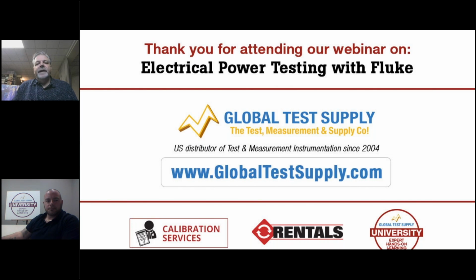If I need those accurate standards to justify a decision being made for product quality as a part of a quality program, or if I'm trying to satisfy a customer that what I'm doing or what I'm making is correct, that's definitely an application where you need to have traceable calibration. If you are questioning your results, saying, hey, I'm not sure if this is right or not, then it's probably best to get it done on a yearly basis. That's what Fluke recommends, a yearly calibration. And I know the GTS can handle that for you. So feel free to reach out to them anytime you need calibration on any test gear, not just power quality.